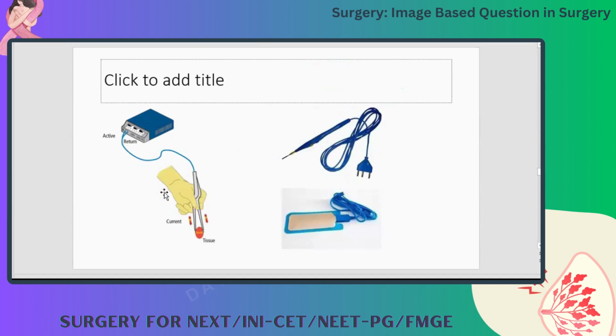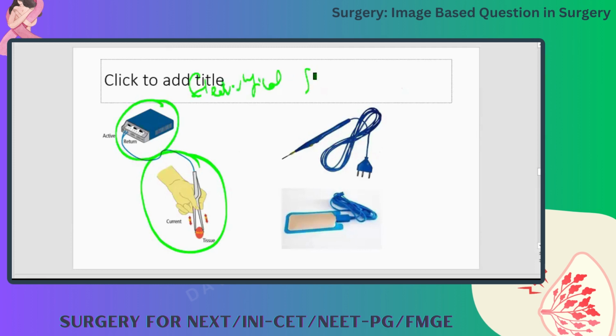And what is this? Diatherm. Diatherms and monotherms. Yesterday we were discussing in QR. This is monopolar, bipolar diathermy. It's an electrosurgical generator. We call it an electrosurgical generator. It has a bipolar, 2 arms. It has a monopolar, single arm.